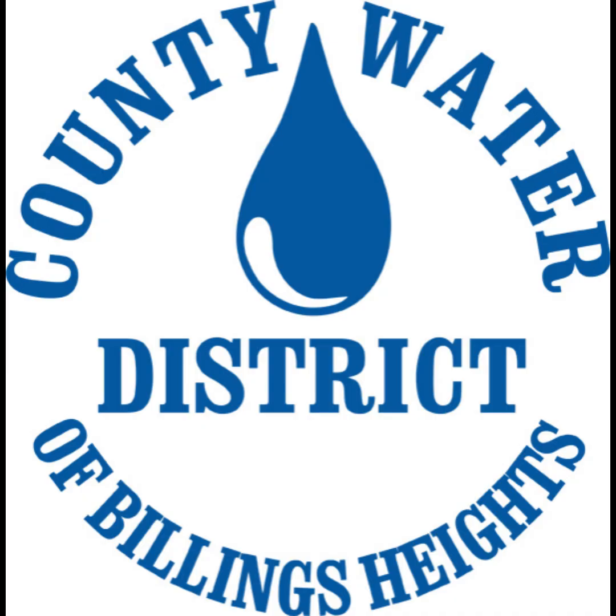Alternative 5B includes installing a 24-inch and a 12-inch transmission main. It is displayed in handout number 6. It'll include installing about 4,000 linear feet of 24-inch transmission main and about 5,500 feet of 12-inch PVC transmission. As part of this alternative, St. Andrews will still need to be in operation, but it wouldn't be operated as much. This alternative is viable since all the pressures are above 20 psi. It has a total capital cost of around $6.95 million.